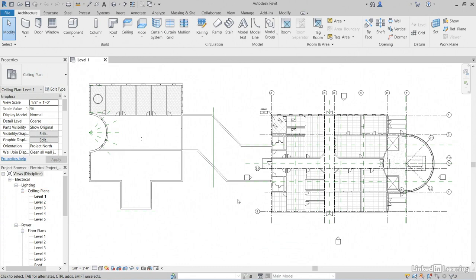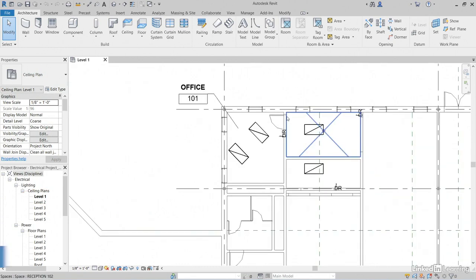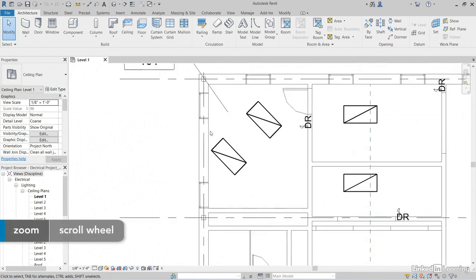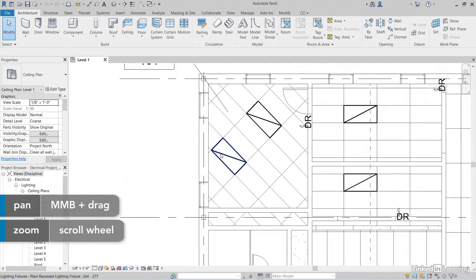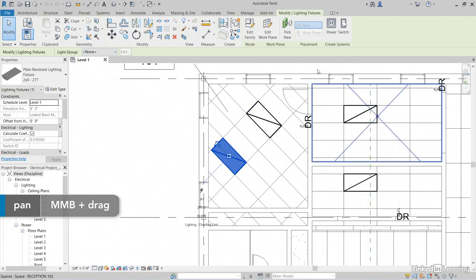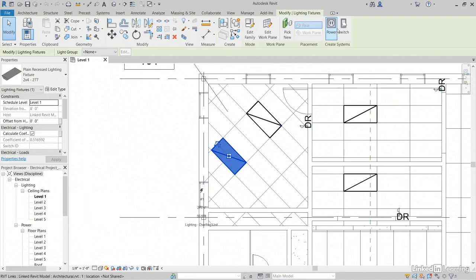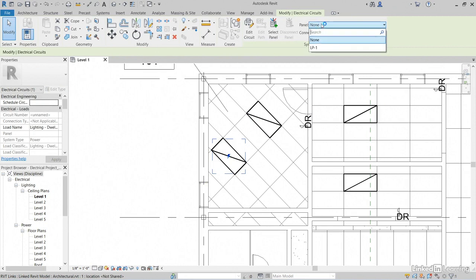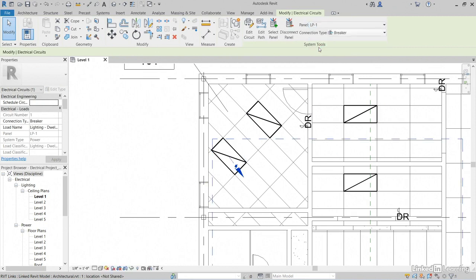Now remember, we had to add a special panel that's going to accept the 277 volts. Let's go into one of our lighting fixtures. Select either of these two lighting fixtures in our ceiling. Notice, because it's a lighting fixture, we can create a power and a switch circuit. Let's click power. Notice for connection type, it's not applicable because we have to select a panel. The only compatible panel is going to be LP1. Now the connector type will be a breaker.